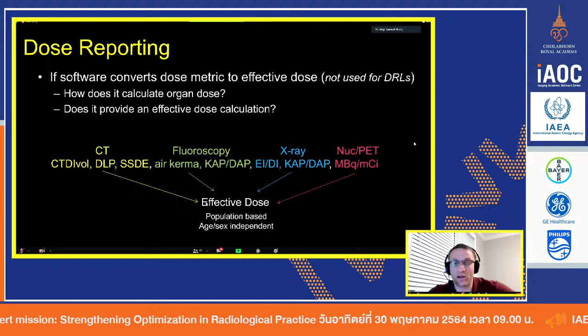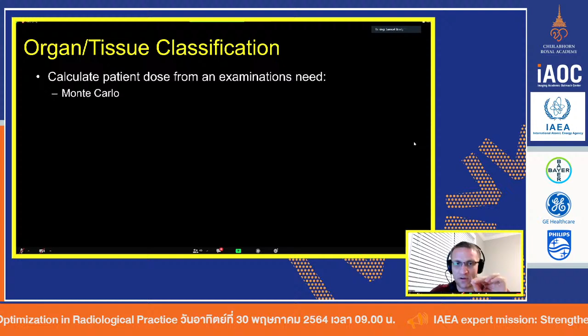Some of the more sophisticated software will allow you to go beyond CTDI-vol, beyond effective dose, and actually start to estimate what the true patient dose is. And the only way to do that is if you use Monte Carlo. And so the system has to be able to calculate the dose to the organ if you want to know what the patient dose is.